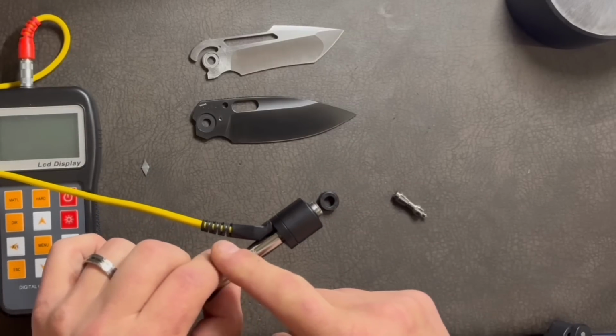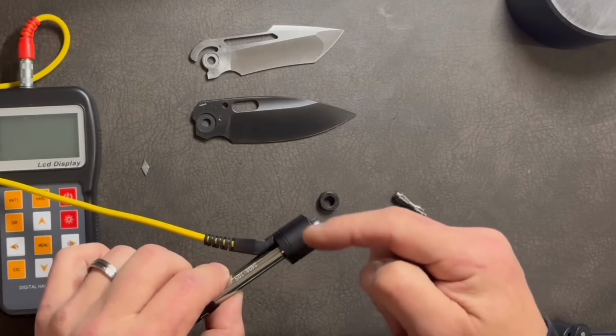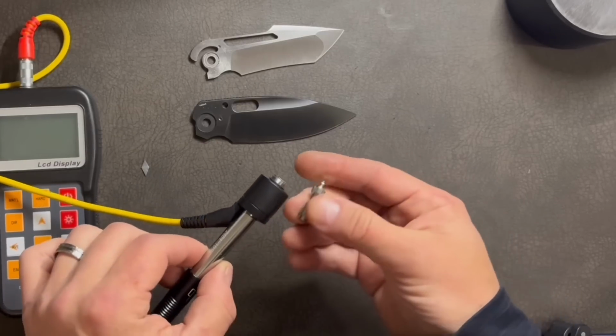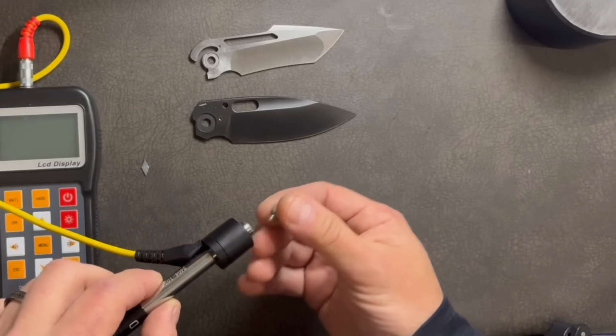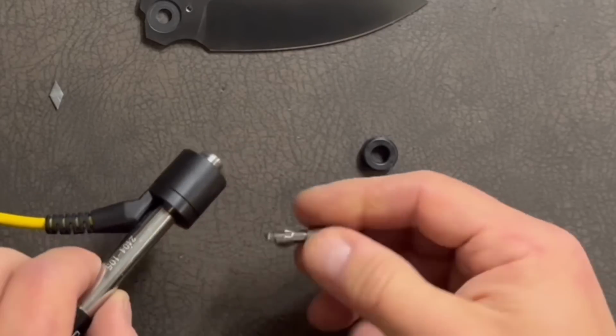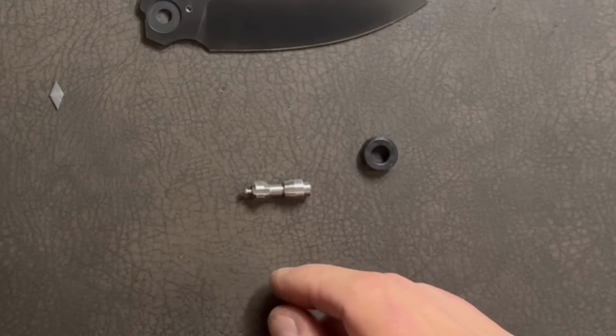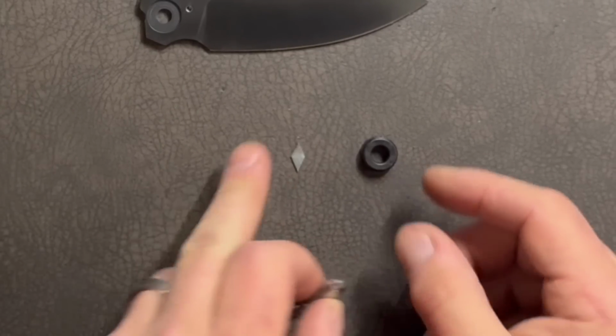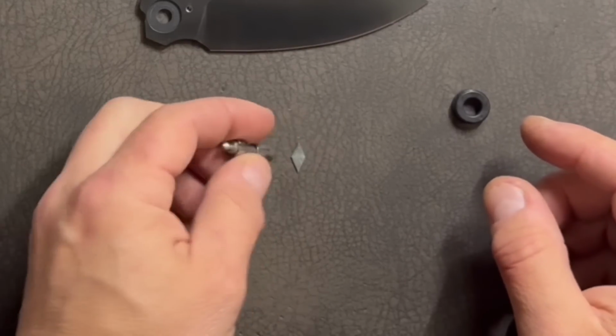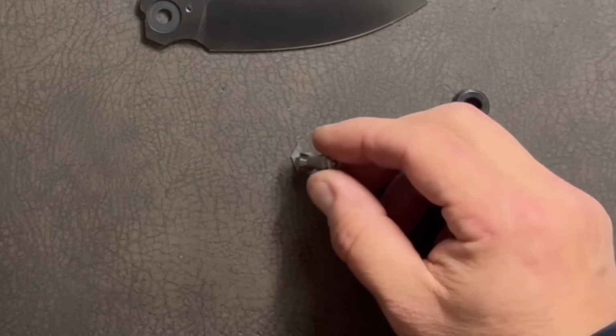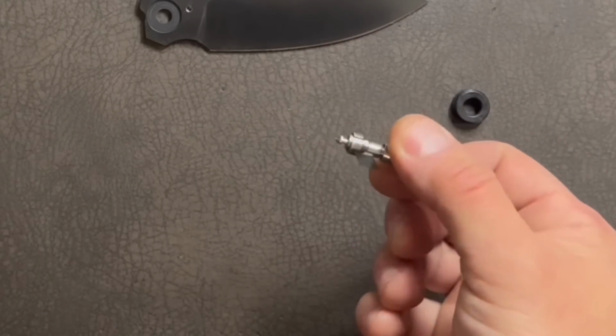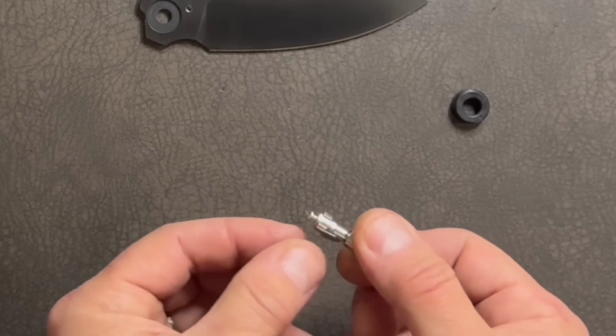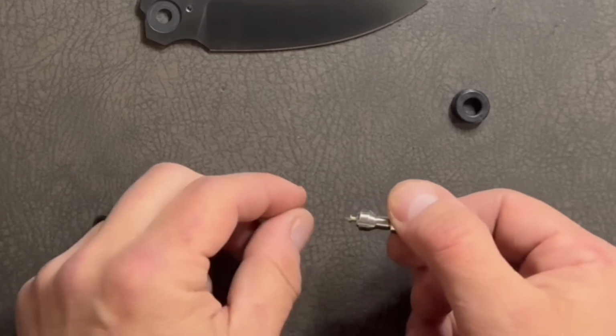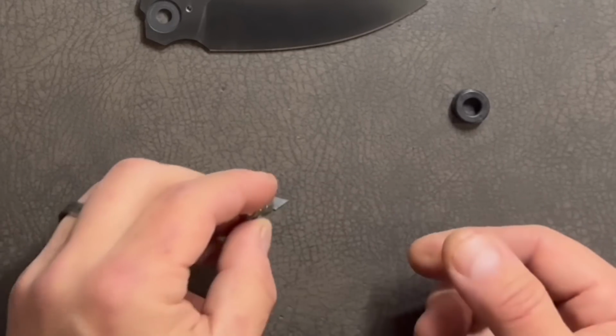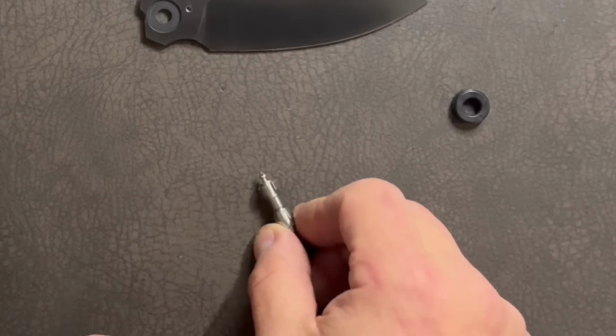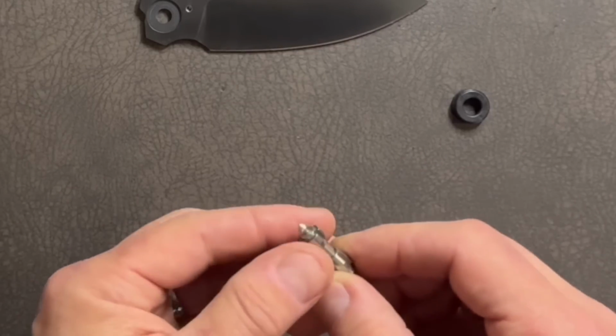Inside the probe, there is an electromagnetic coil. The power is supplied from the batteries, goes through the coil, creates a magnetic field that this probe travels through. And that means that inside this probe, there is a magnet. That magnet interacts with the magnetic field in the coil, and it's just a random piece of metal, so I can't pick it up on the tungsten side, but the opposite side is magnetic because that magnet lives in there, and it creates distortion in the magnetic field, and that's what the computer uses to estimate the return velocity of the probe when it bounces back. That's how it works.